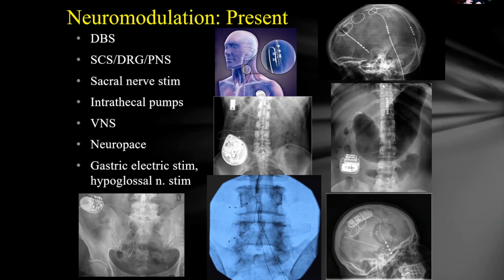And you can see in the lower right corner the picture of the NeuroPace device. For the processor itself, part of the skull is carved out, and that processor goes in there. You can see the larger electrode, the sensing electrode, on the cortical surface. The more direct, straighter electrode with the smaller contacts is the effector electrode, the DBS electrode. So it connects a DBS electrode to a sensing electrode through a processor, senses when you start to get epileptiform cranial activity, and then it will deliver stimulation, which will abort the seizure. That also has been very effective, but still a very gross design.